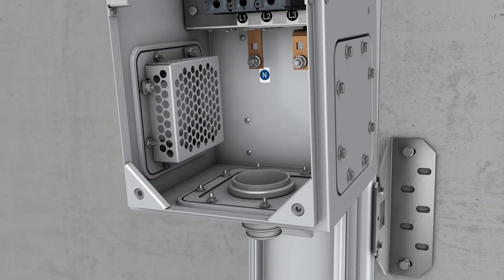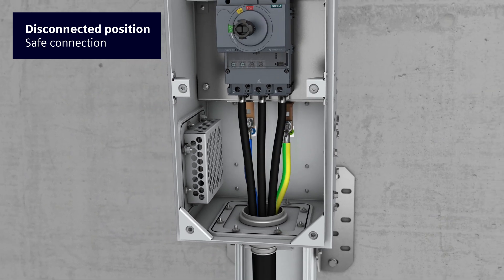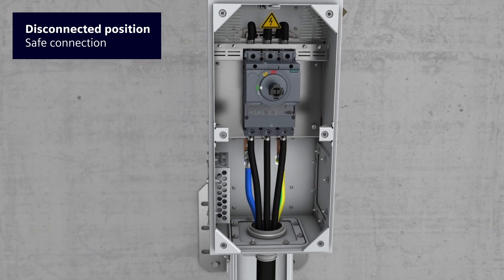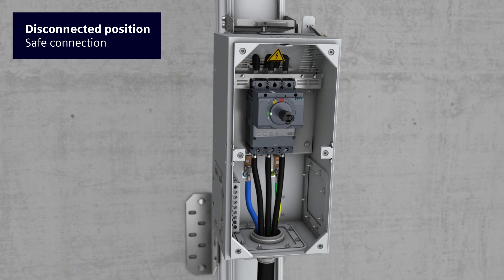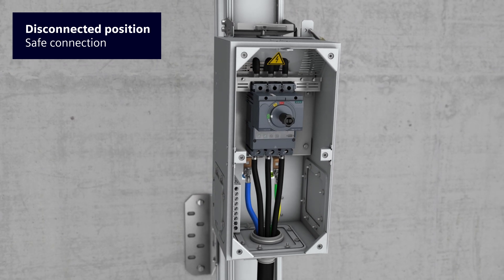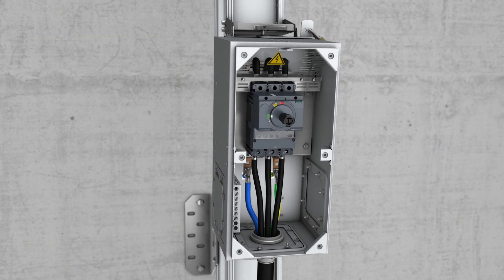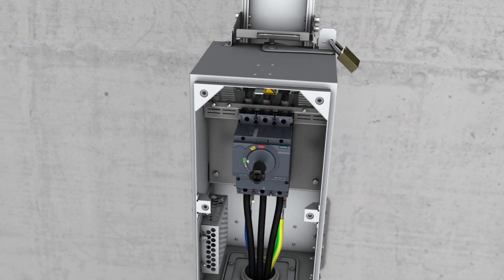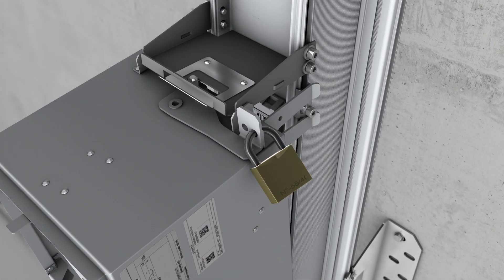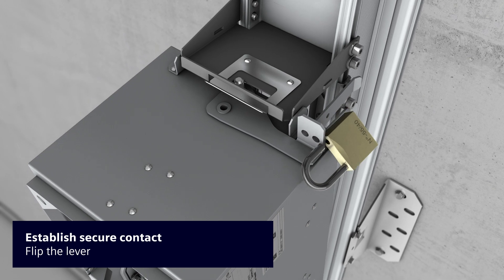The electric connection of the consumer to the tap-off unit can now be carried out safely by simply connecting the consumer cables. Electric contact between the tap-off unit and the busbar system must not be established before all cable connections have been completed and secured.